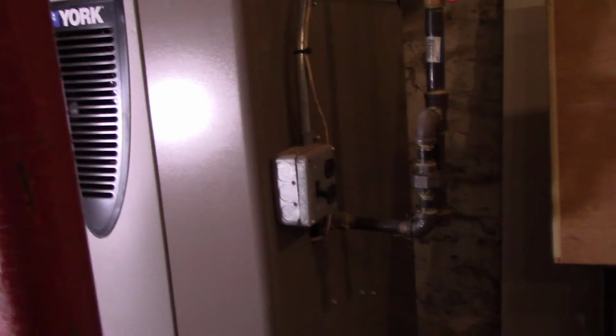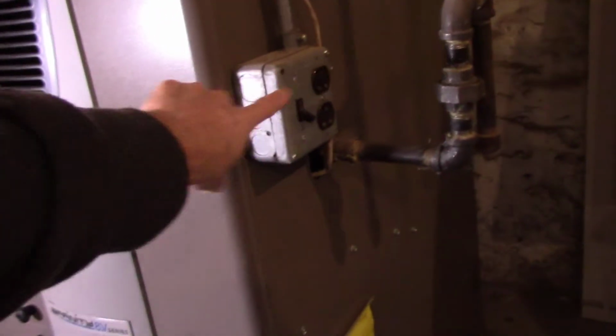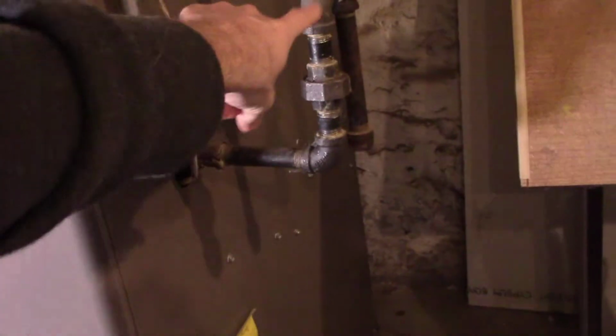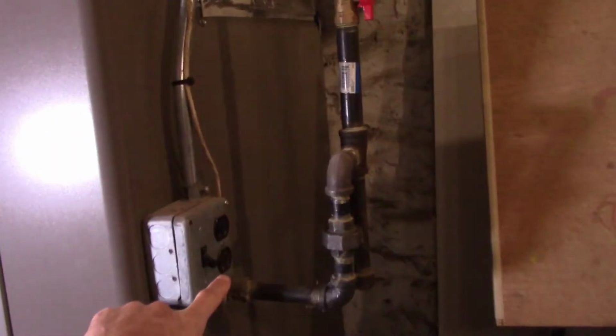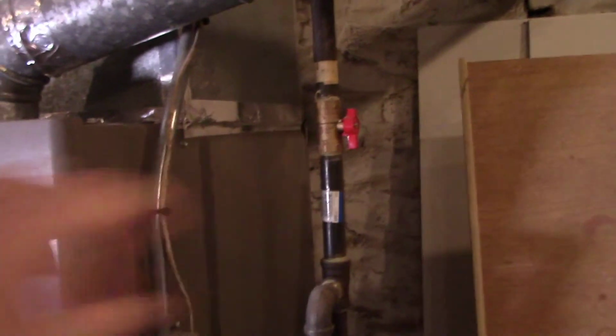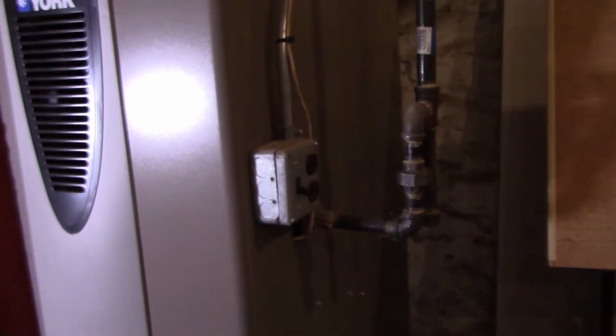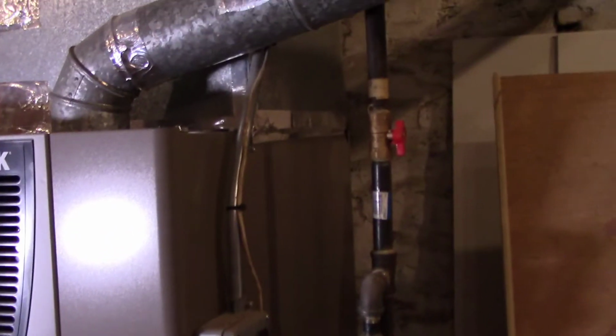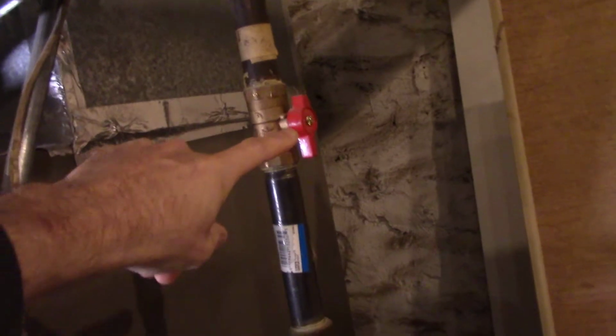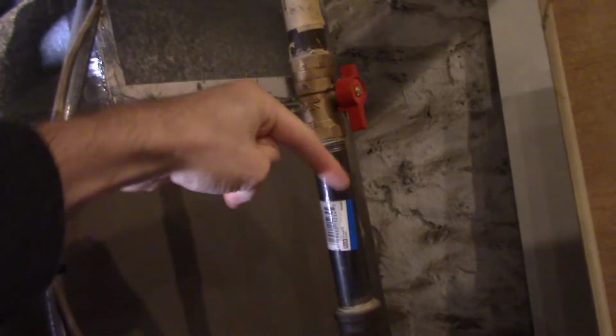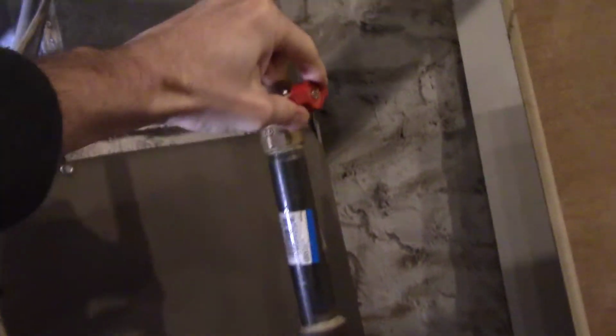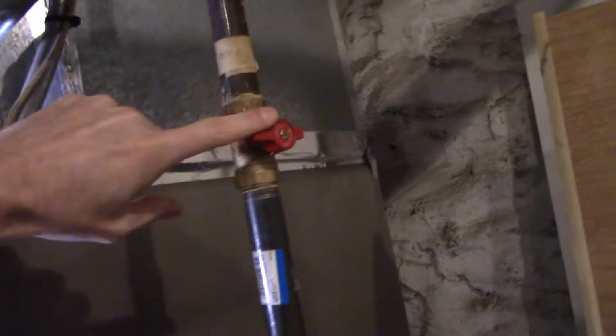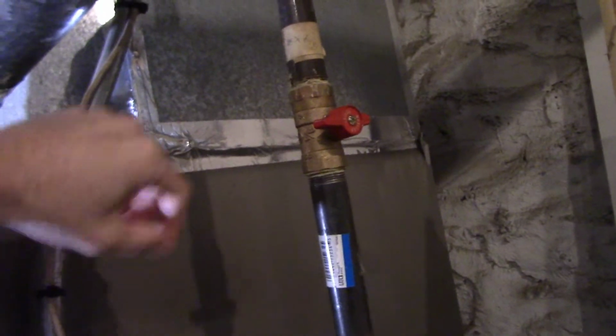So on a typical gas furnace, you'll likely have a switch on the outside and a gas piping going in with some kind of shutoff. So the first thing we're going to do is just determine, do we have gas on? And we do. The handle is parallel to the gas flow. If this was turned like this, perpendicular to the flow, that means it's off.